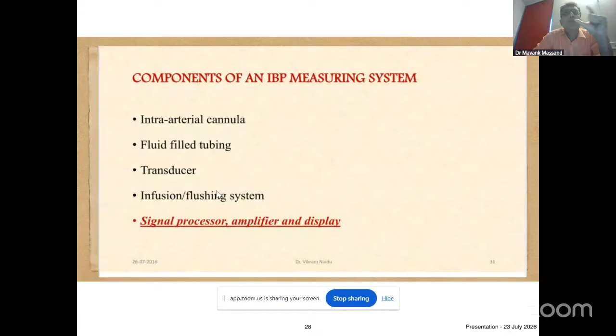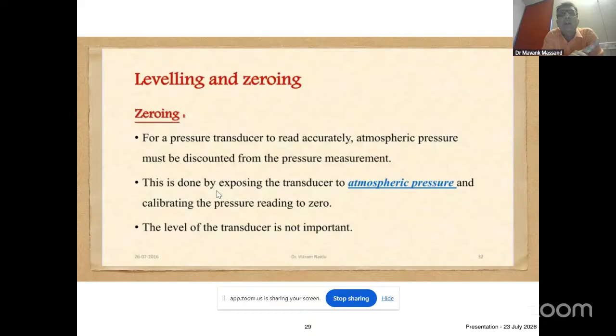Correct? (Hindi: That is already there) and it is loaded. Frequency and damping coefficient are also preloaded. This step is extremely important. Now, once we have set up the system, we expose the transducer to the atmospheric pressure of 760 millimeters of mercury, and that reading is regarded as the zero reading for that particular amplitude. Okay. Now, at this particular point, when we are zeroing the system, is the leveling important? No. After zeroing also, we can level the system.